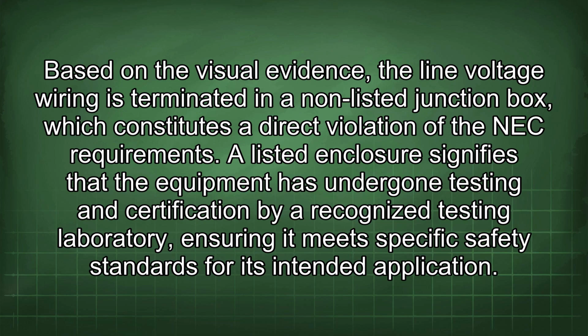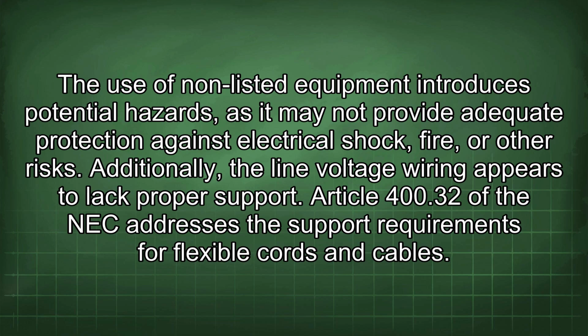A listed enclosure signifies that the equipment has undergone testing and certification by a recognized testing laboratory, ensuring it meets specific safety standards for its intended application. The use of non-listed equipment introduces potential hazards, as it may not provide adequate protection against electrical shock, fire, or other risks. Additionally, the line voltage wiring appears to lack proper support.